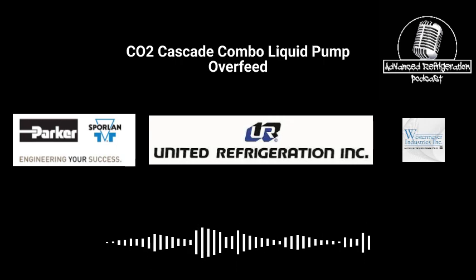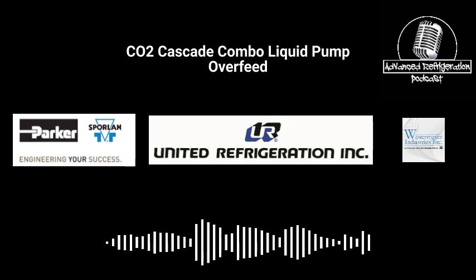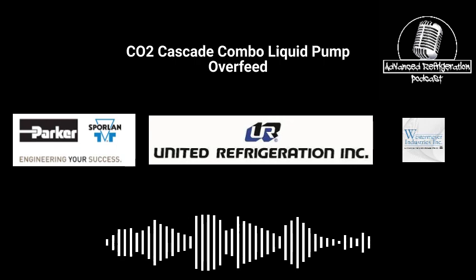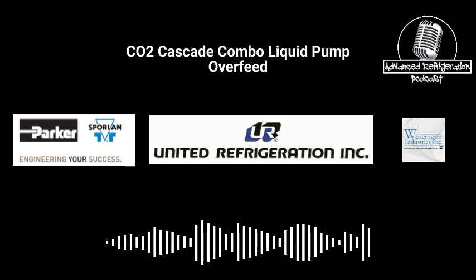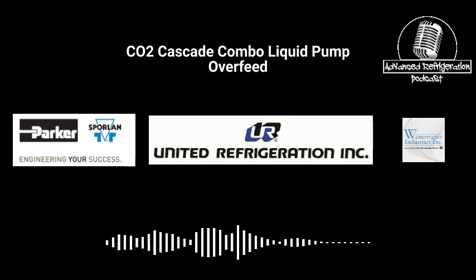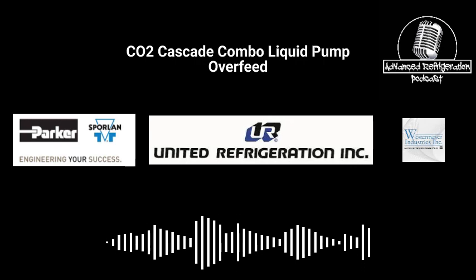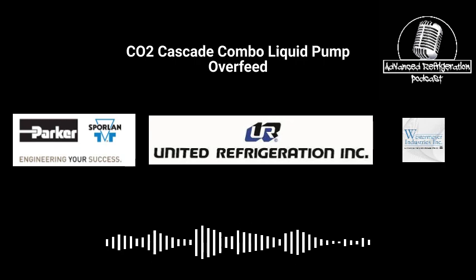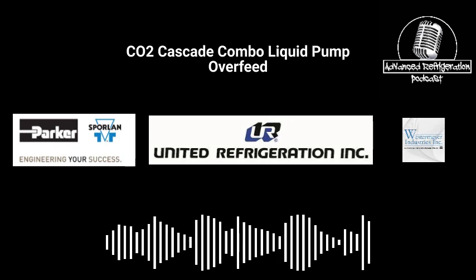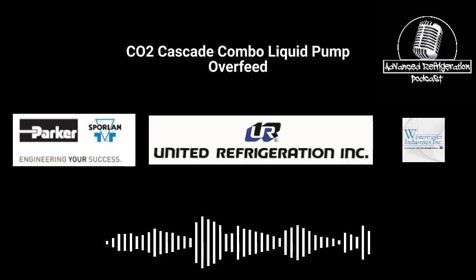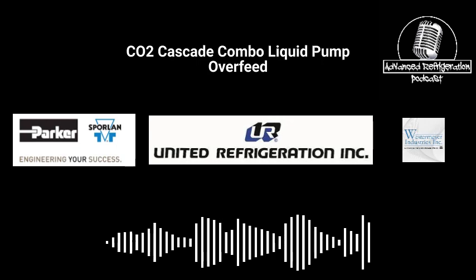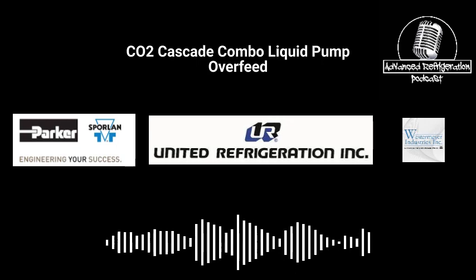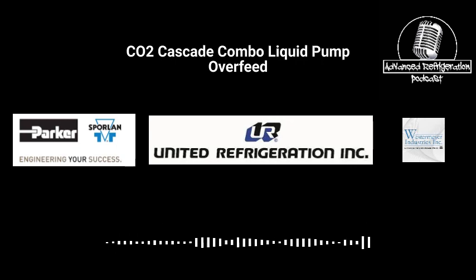But again, this type of control is one where you'll have to float the vessel a little bit, because just like the Walmarts, if you're running minus 20 all the time, you get a bunch of cases shutting off. Now that load drops off and you get spikes, because when that load comes back on, it's going to spike the liquid separator/receiver in pressure, and then the Cascade rack has to catch up to it. Gotcha. So that's where you're going to have these issues. You want to float that Cascade rack up as high as you can get it to keep all those cases running. But at the same time, you've got to watch because you don't want to start high heading the low temp discharge of the compressors, because you've got that fine line to walk. Yeah.